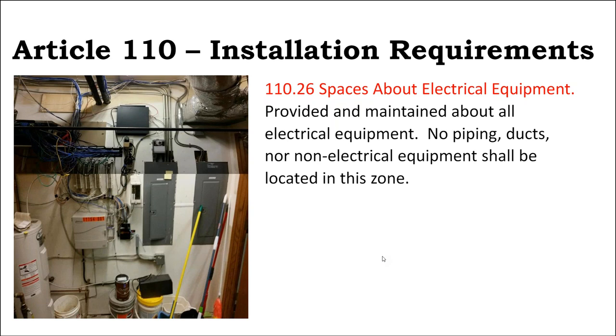And it becomes uncomfortable to get into that alcove and work there because you've got to be hunched over. That space was not large enough for a worker to stand right in front of the working space and do their job. So not all rooms can be converted into battery storage or electrical rooms or inverter rooms, because if they have a low ceiling that's not tall enough to stand in, it would be more code compliant to have a box that's detached from the building where there's open airspace ahead of you, rather than to tuck the batteries into an alcove in the building foundation, if that alcove is not going to be tall enough for someone to stand and work in.